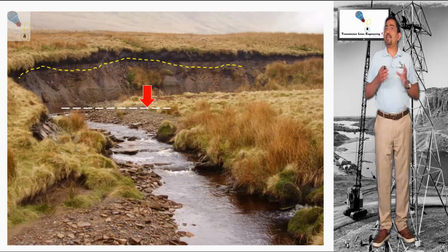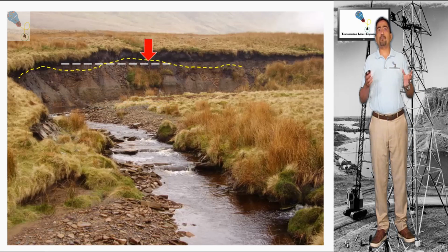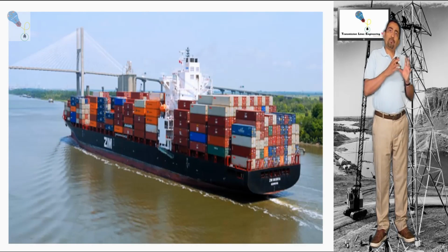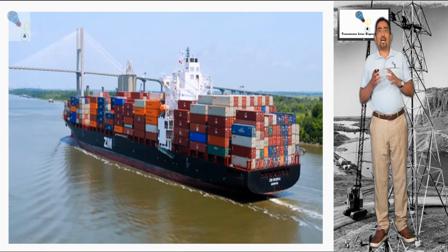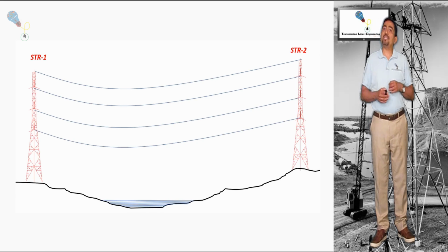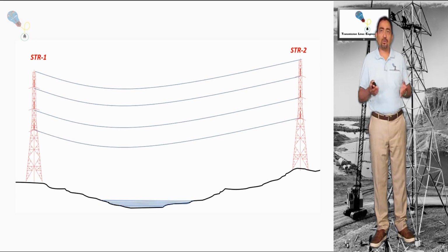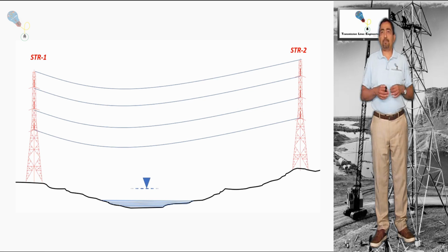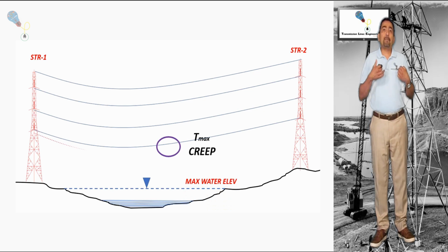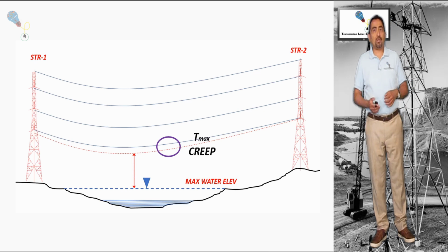In the case of great flow rivers or those of considerable width where there is vessel traffic, it is a completely different process, since in addition to identifying the environmental requirements and river banks, it is necessary to contact the administrative agency to consult a very important data for this type of crossings called the water's maximum expected level, which will provide the information of what elevation the maximum level of water has been registered, and this data is taken into consideration for the vertical clearances for the crossing.